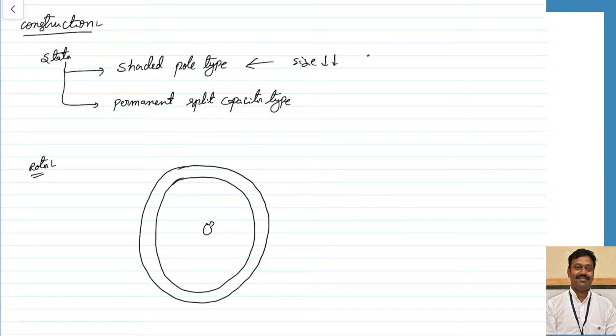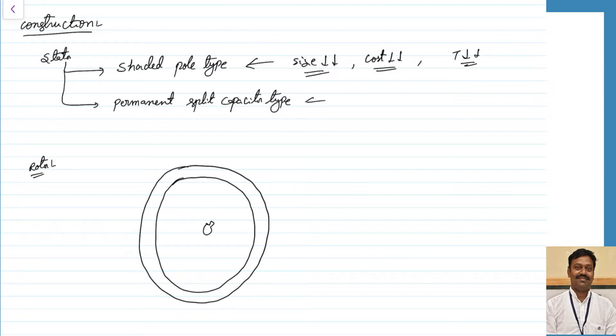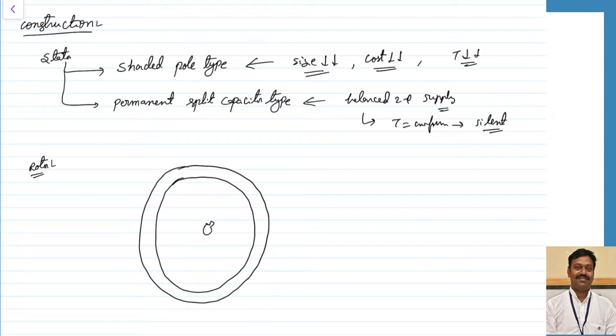The shaded pole construction is done where the size should be less and cost should be less. The disadvantage of the shaded pole motor is the torque will not be uniform because the rotating magnetic field produced is not uniform. Automatically the torque produced will be less and not uniform, so silent operation will not be possible because of non-uniform production of torque. With the permanent split capacitor type, we can produce a balanced two-phase supply, giving a balanced rotating magnetic field of constant magnitude. Due to this the torque will be uniform and operation will be more silent compared to the shaded pole.